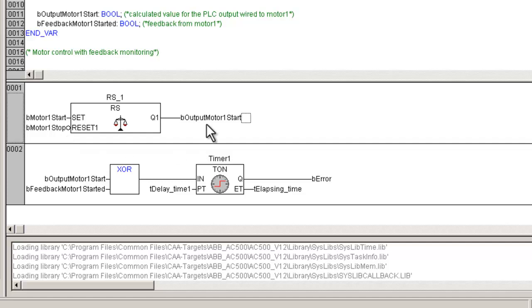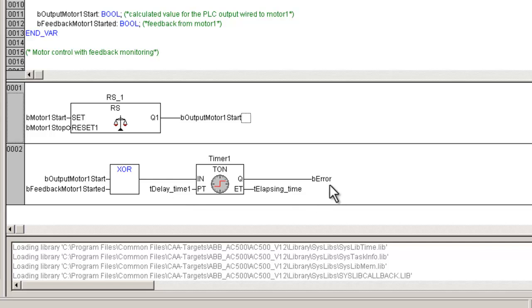The motor is started by pressing a normally open type start push button, and stopped by a normally closed type push button. The output of this logic drives the motor contactor, and there is a feedback from the motor to ensure that the motor is correctly operated in the field. If the motor contactor does not get energized within a stipulated time, the output logic will be made off to de-energize the motor. Therefore, we have three inputs and one output which would be simulated from the visualization screen.